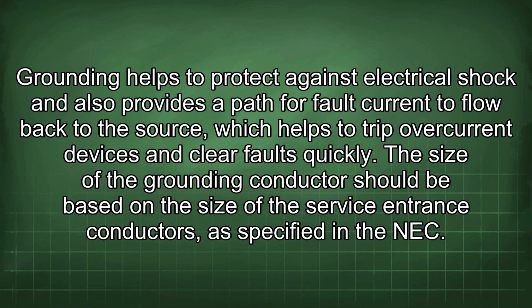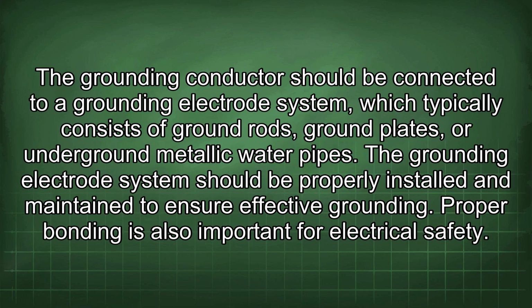Grounding helps to protect against electrical shock and also provides a path for fault current to flow back to the source, which helps to trip overcurrent devices and clear faults quickly. The size of the grounding conductor should be based on the size of the service entrance conductors, as specified in the NEC. The grounding conductor should be connected to a grounding electrode system, which typically consists of ground rods, ground plates, or underground metallic water pipes. The grounding electrode system should be properly installed and maintained to ensure effective grounding.